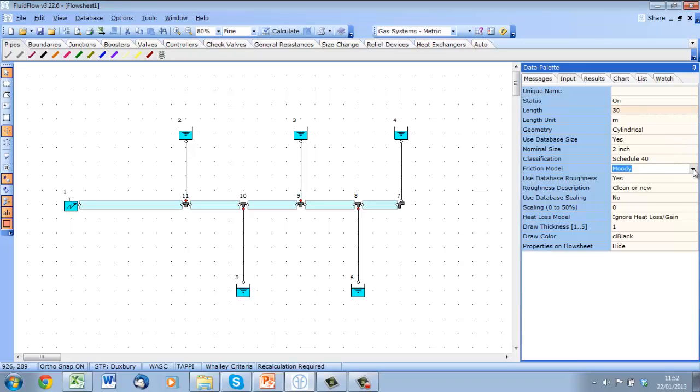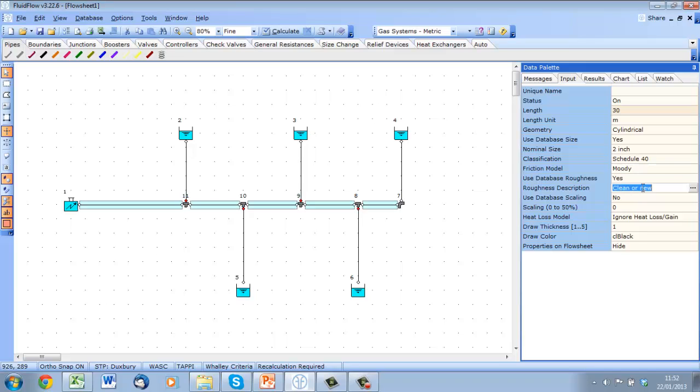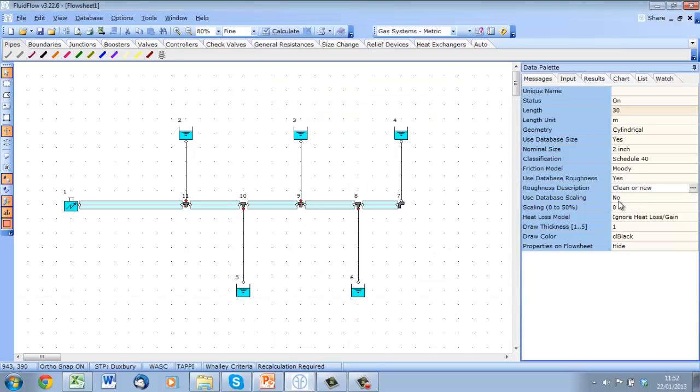I will not worry about pipe size just now because we will look at that in more detail later. Here we can also specify the friction loss model. We can use either Moody or Hazen-Williams or you can directly enter the Darcy friction factor. You can also select the surface roughness from our database or again enter your value directly.